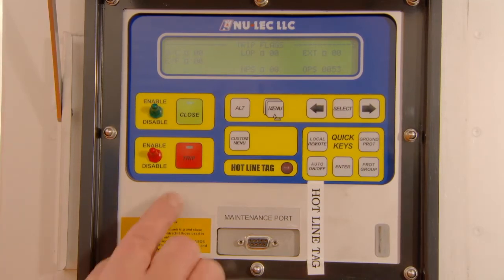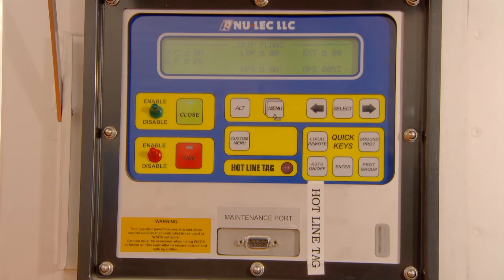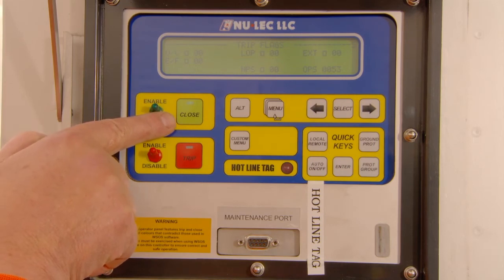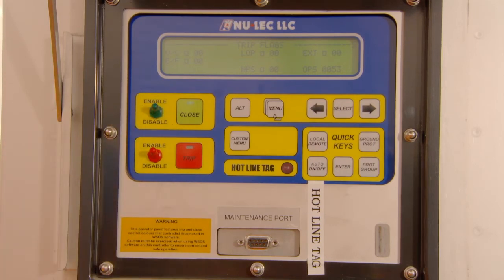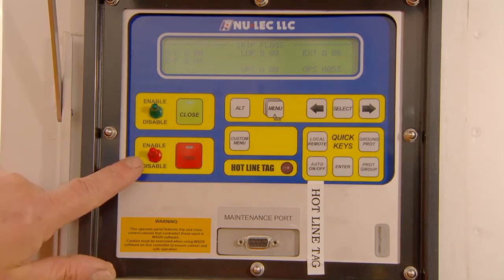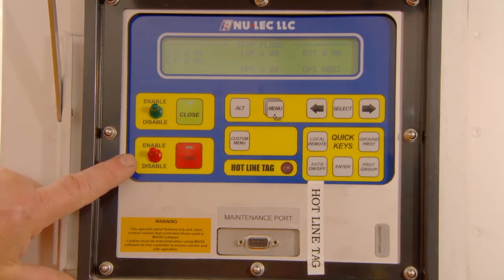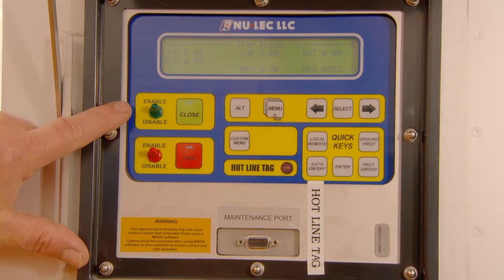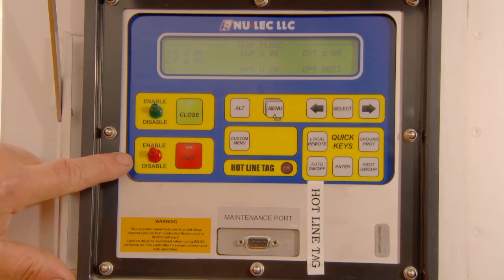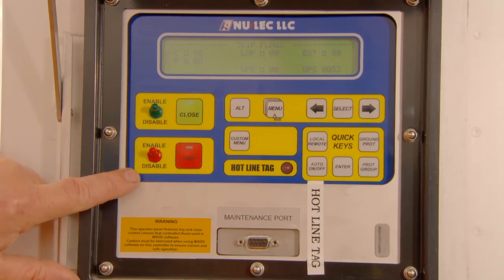First, we have the red trip button, which will trip open the recloser. Above it, we have the green close button that will close in the unit if it has tripped out. Beside both the open and close buttons are the enable and disable switches. Ensure that these switches are set in the enable position. If they are turned to the disable position, the trip disable will not allow the unit to trip.